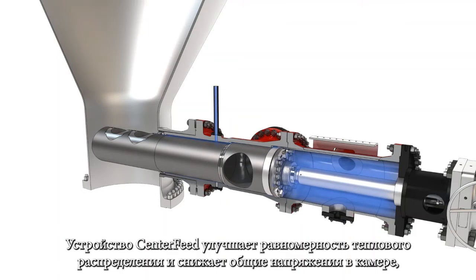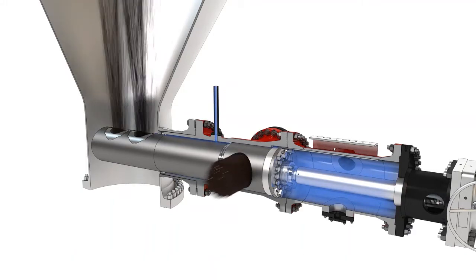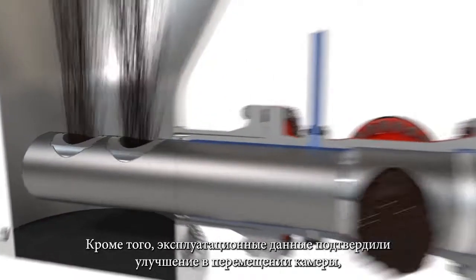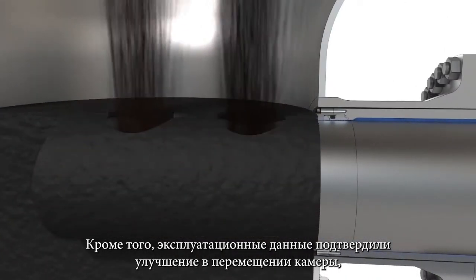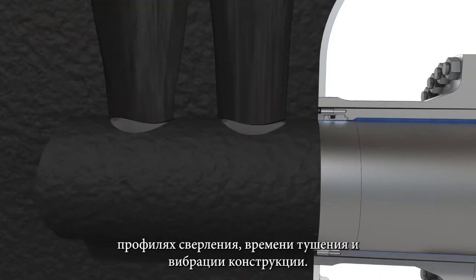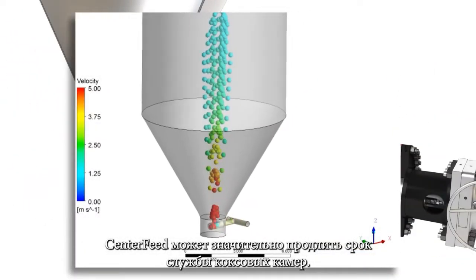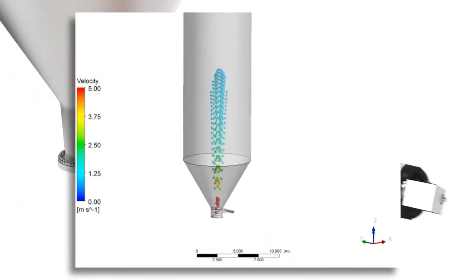The CenterFeed injection device combined the side feed design with the advantages of traditional bottom feed. The CenterFeed improves uniform thermal distributions and reduces overall drum stresses, local hotspot formations, and top head blowouts. Operational data also shows improvements to drum movement, drilling profiles, quench times, and structural vibration. The CenterFeed can significantly extend the operational life of coke drums.